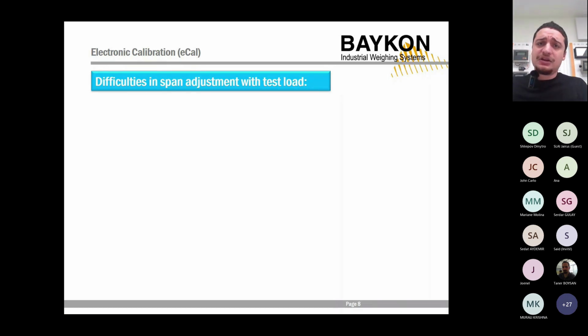And these scales' capacities are 30 kilograms, 60 kilograms, maybe 100, or extremes are also possible, 200 kilograms. And when that's the case, finding 10% of that much weight or 40 to 50% of that much weight is not that hard. Because if you have a scale that measures 30 kilograms max, the amount of weight you need is going to be 3 kilograms. It's pretty straightforward. You have a scale, you have weights, and you have a procedure that you need to follow. In the worst case scenario, it's going to take a couple of minutes.